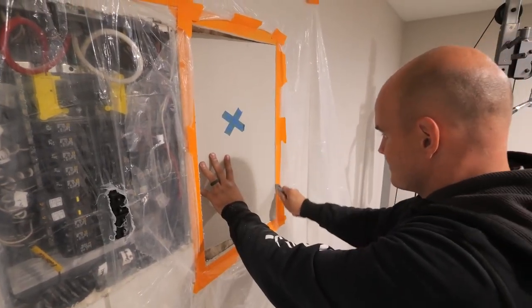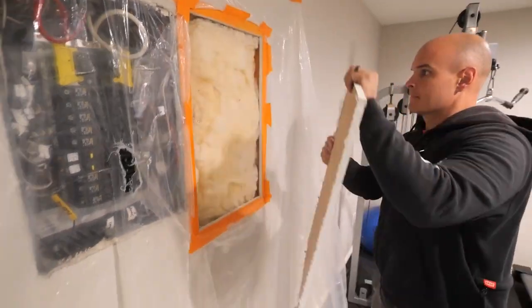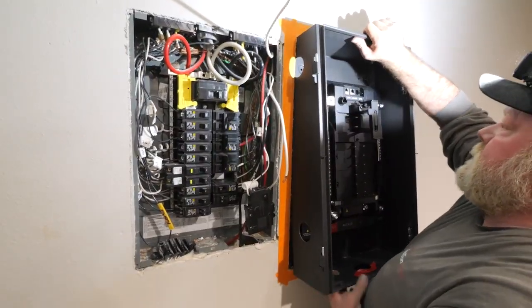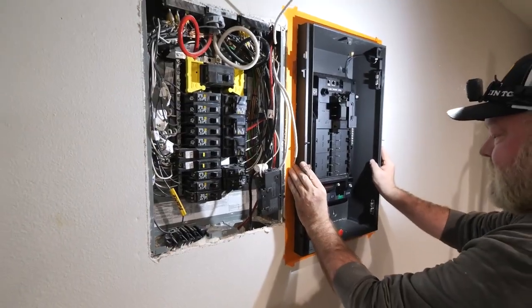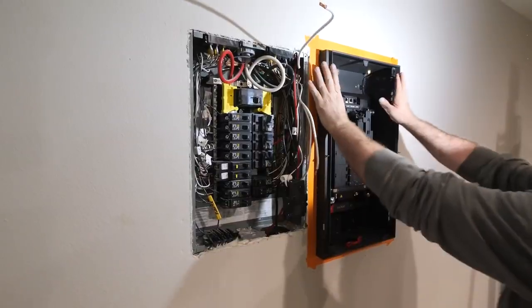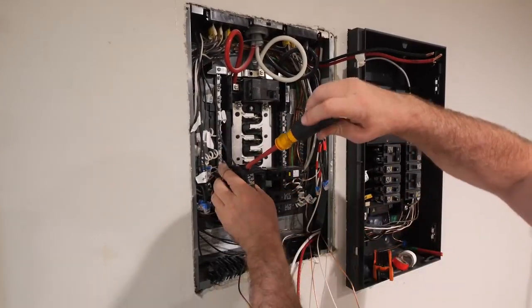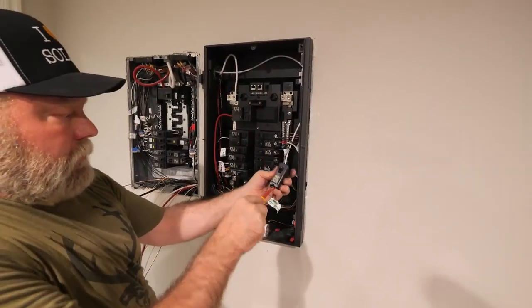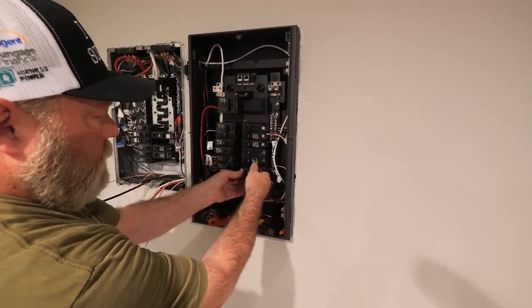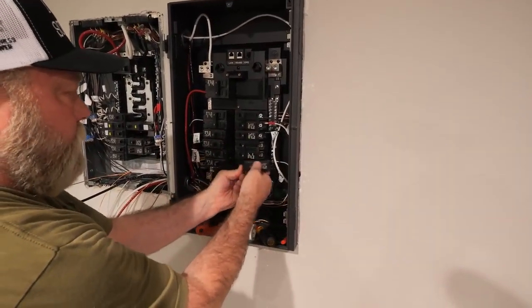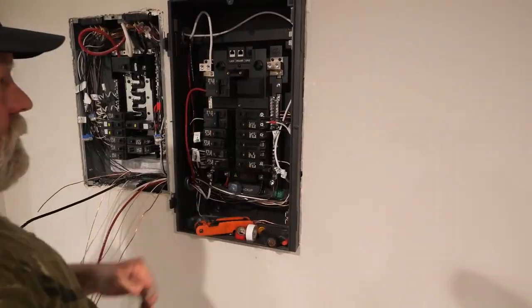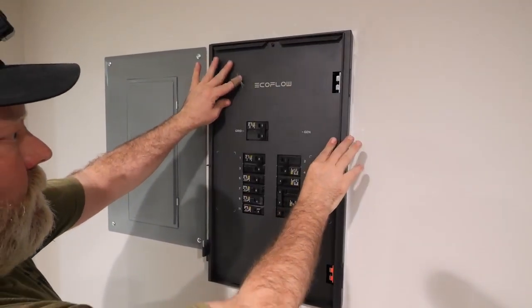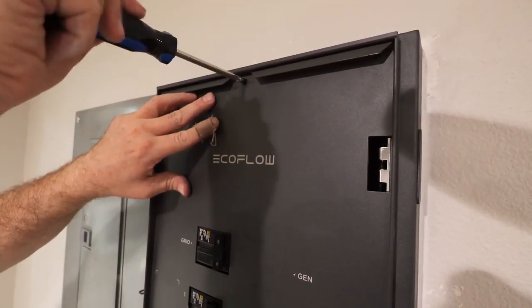Running wires is probably the most time-consuming part of this whole project. The Ecoflow Smart Home Panel gets recessed into the wall, and a qualified electrician can move all of the breakers from the old panel into the new panel. The new panel allows me to control each breaker individually from my Ecoflow app, and the individual breakers run on grid, on battery, or even off a 12 kilowatt gas-powered generator, since there are 5 different energy inputs for this panel.